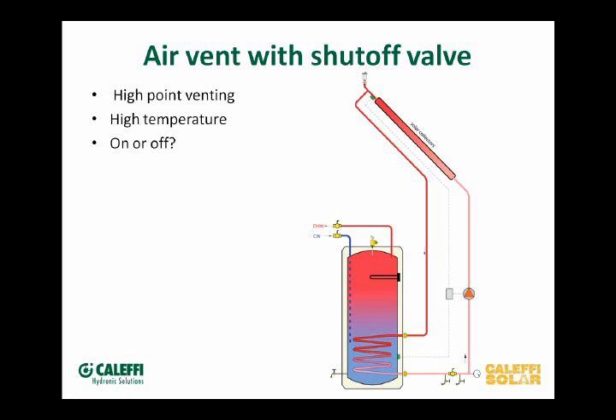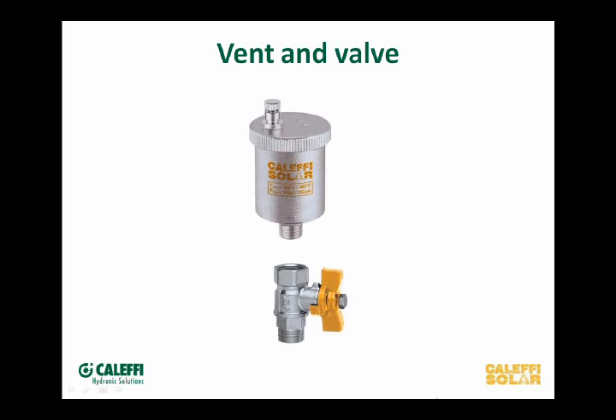The air vent also lets you have automatic air removal for startup or the first couple days of running. There's a picture of it here — we've got a half-inch ball valve with male-by-female thread so it screws right into that cross fitting or T without needing a nipple. The air vent screws right into it on the other side, and the top comes off so it's serviceable. It's rated 150 PSI and 360°F, with viton seals instead of the EPDM that a typical ball valve might have.